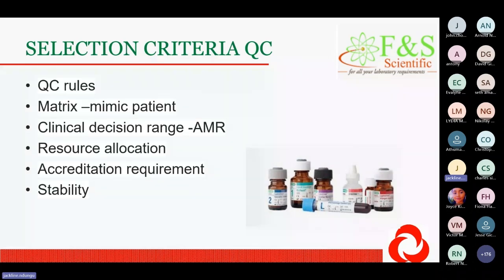So for example, if you are not able to run 3 controls in a row, some standards will allow. As long as you have done it on the lower side and on the higher side, you have controlled your system. When resources allow, please make sure that you do. You choose your QCs again; you don't go for the very expensive. You don't say we must get Bio-Rad when you can get this, or you must get Roche when you can get this, or you must get Sysmex when you can get this. I'm just giving examples.